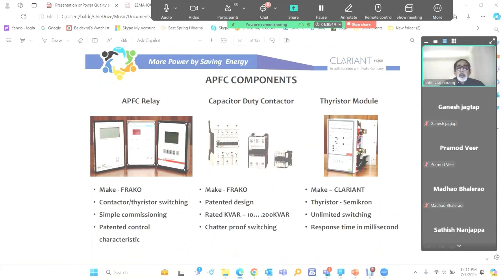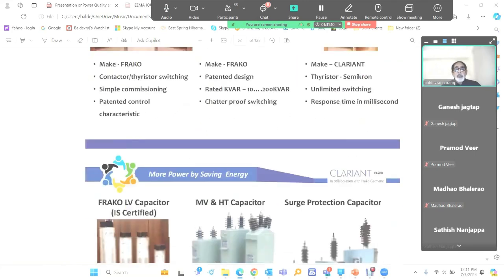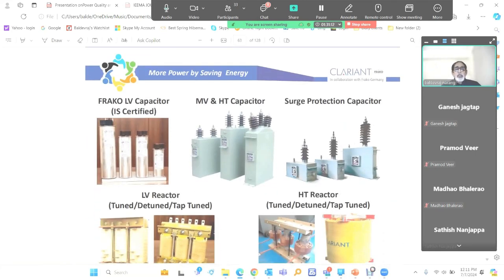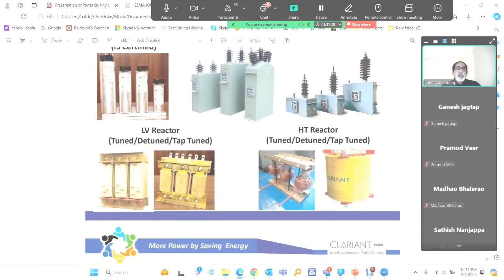So these are photographs of some contactors, and this is a thyristor module, because these days APFC panels are through thyristor switching. It is real-time switching, almost 20 to 40 milliseconds we can switch on. Then these are the controllers. These low voltage capacitors are imported from Germany. This medium voltage, this is surge protection capacitors. And these are the reactors, we have our own manufacturing. This air reactor, medium voltage.